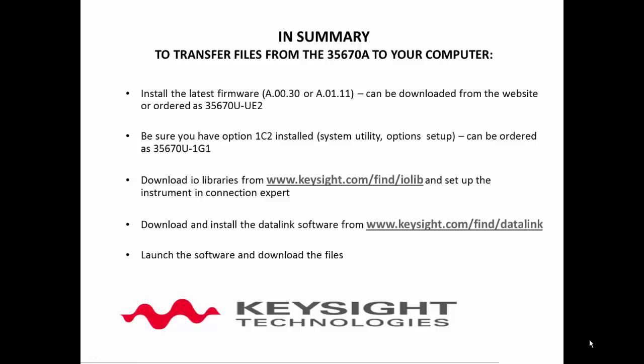To summarize the process for transferring files from your 35670A to your computer, simply follow these five steps. One, install the latest firmware on your instrument, either A.00.30 or A.01.11. Two, be sure you have option 1C2 installed on the instrument. Three, install the IO libraries on the computer and configure the instrument in Connection Expert. Four, download the Datalink software from www.keysight.com/find/Datalink. Five, launch the software and download the files.